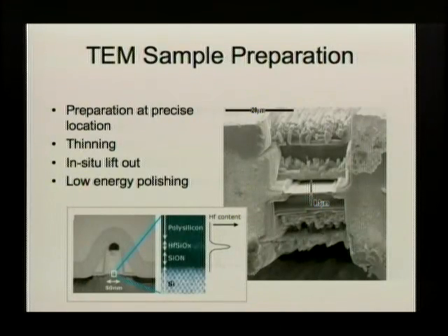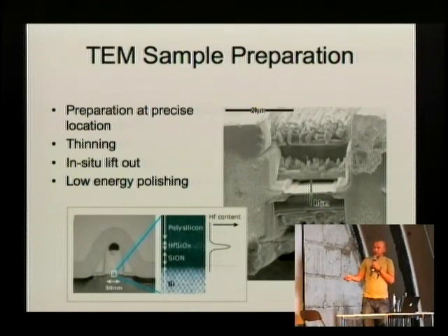So if you're interested in very small structures, you can either reduce the energy of the beam, which unfortunately reduces the resolution, or you can just cut very thin slices. And the focused ion beam allows you exactly that. For example, if you have a substrate where you know there's a transistor in the middle, and you have pinpointed that this is the transistor that probably failed, you would like to see why it failed, what happened. You can use this focused ion beam to cut out a small lamella. Then you would take this lamella with some manipulator, lift it out, put it either in the same device or in a different transmission electron microscope, and then you can really see a slice through the transistor, and you can, if necessary, go down to atomic resolution.